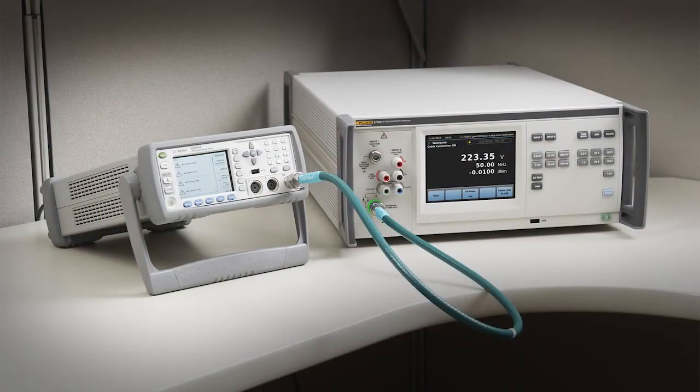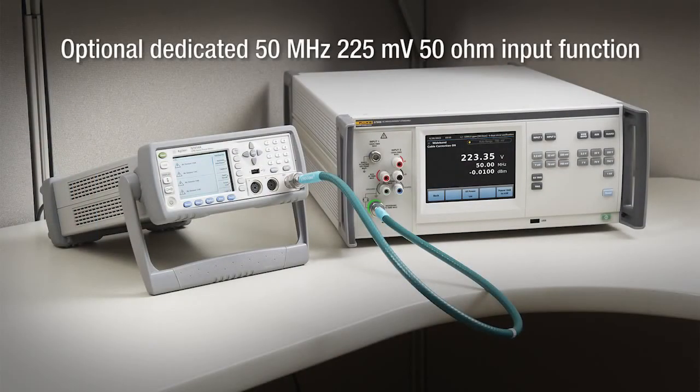A dedicated special purpose 50MHz, 225mV, 50 ohm input function is available as an option for measuring RF power. The option is spot-calibrated at the end of a precision level or phase-stable metrology grade cable. It calculates the measured power with 50 ohm load.